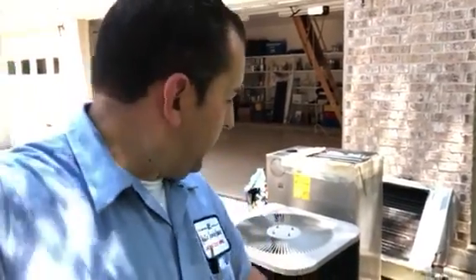So in reality, after you add up all that deterioration it has, it's probably maybe a 2.75 or maybe a 3 ton. Plus it's from 1997, so it's 26 years old, more or less. So it was time to get it changed. So we're replacing it with a brand new system, indoor and outdoor, and they'll be happy customers.